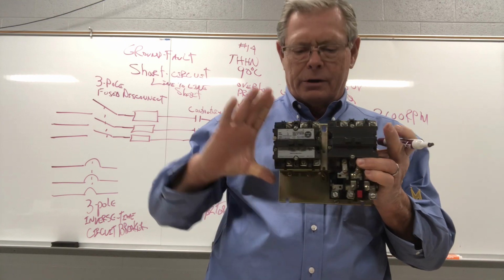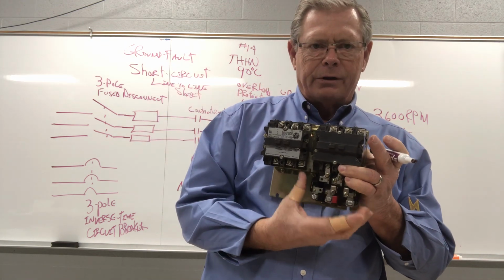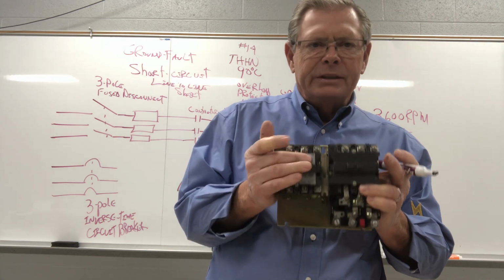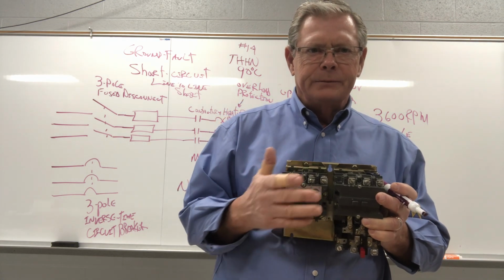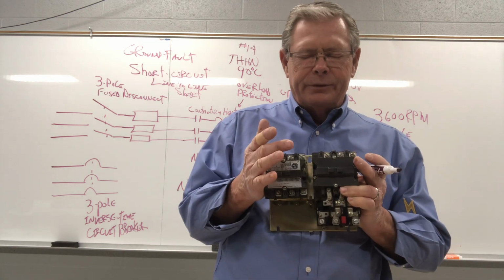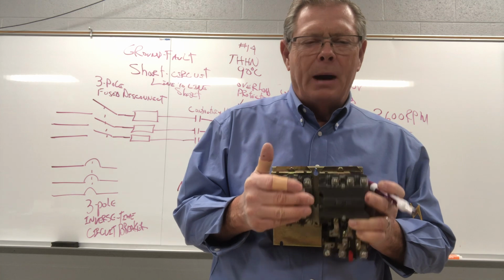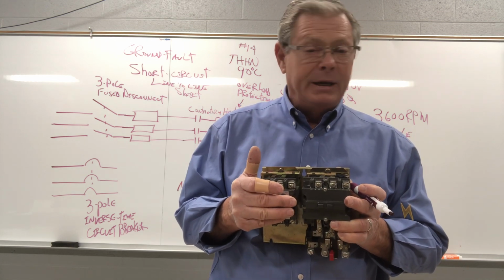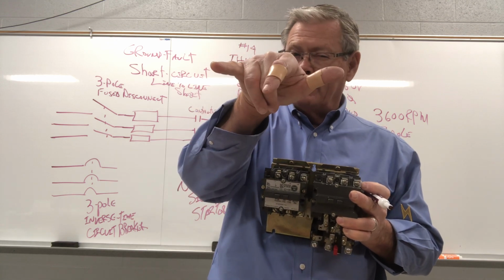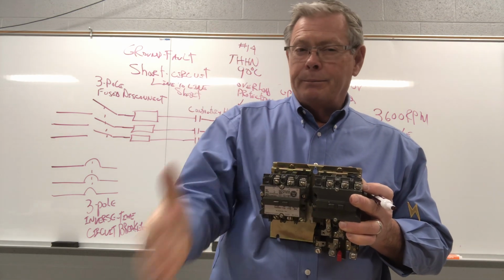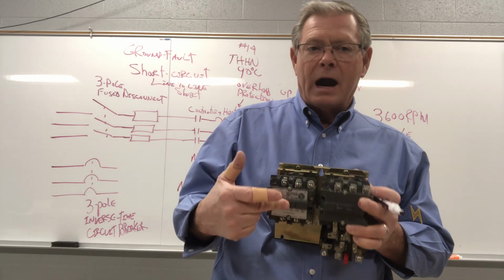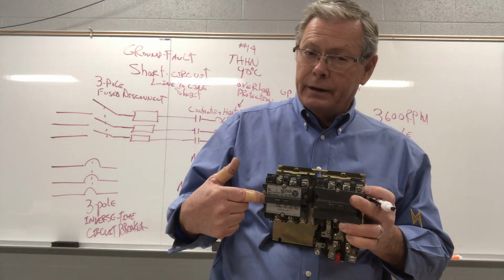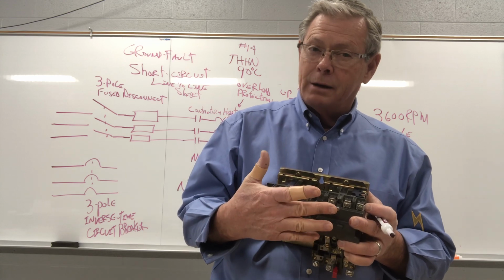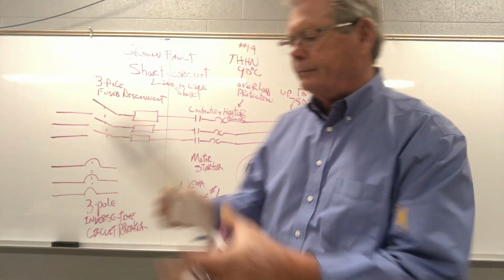These contactors on a starter, here's contactor, here's contactor, this is a reversing starter, here's the overload block right here. These contacts are only good for so many amps, okay? So for so many amps, it's at the application voltage. Power equals current times voltage, right? P equals IE. So for the same 10 horsepower, if we cut the voltage in half, the current has to double. So the higher the application voltage, the lower the current, and a smaller starter for the same horsepower motor. So, now we know we need a NEMA size 1 starter.